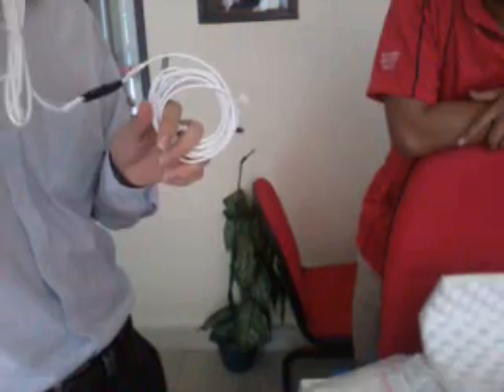Okay. This one is a digital sensor. I can just calibrate the probe. That means I can disconnect this part. I can disconnect this part. Just calibrate the probe on its own, and then I cucuk balik. It doesn't affect the readings on this side. I don't have to calibrate this one. Okay. Just the probe. Yeah. So just the probe only. Okay. So I can cabut.